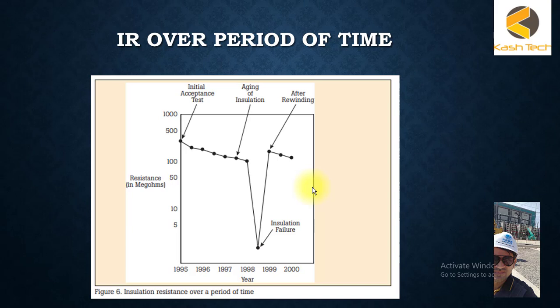Here you can see an example where one equipment is tested and they have kept the record. You can see they tested the equipment first time in 1995, kept the reading, and then tested it gradually. You can see there's a pattern - insulation is going down gradually. This gradual resistance decrease is okay and perfect; there is nothing to worry about.